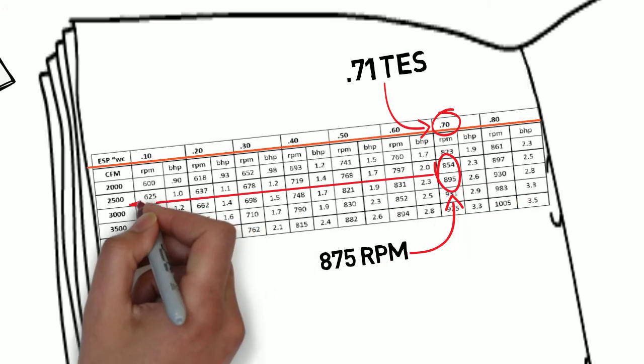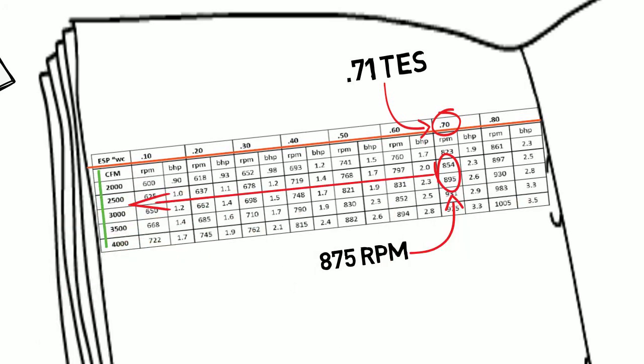We draw a line over to the left. There's our CFM category. 2,000 to 4,000. We're falling right in the 2,500 to 3,000. I'm going to call it 2,700 CFM. This rooftop unit is moving 2,700 CFM of air.